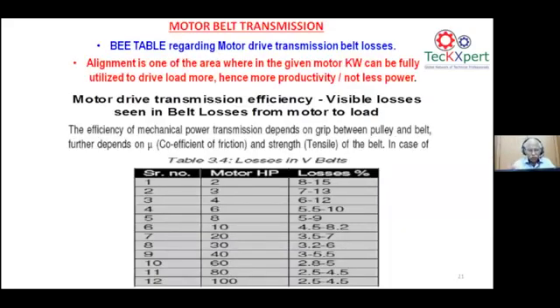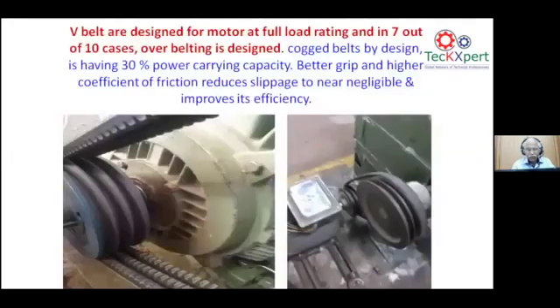So if you see a 2 HP model, the loss on the belts is almost 15%. It is a visible loss. It is definitely measurable between the motor and machine, and it has to be corrected. That is why many of the industries have already changed over from all their existing V-belts. On the right side, you can see the existing V-belt, which is wobbling. And on the left side, you can see the cogged belt, which is more rigid, and the power carrying capacity is 30% more. So it can have optimized sizes of motor and machine pulley. Ultimately, the productivity is improved, the slippage is reduced. That is what we want, and the belt life almost doubles.